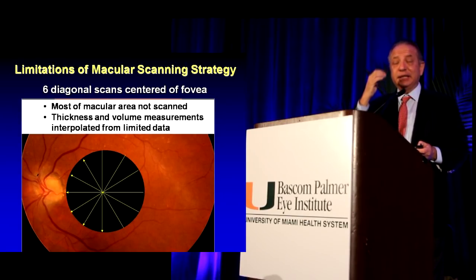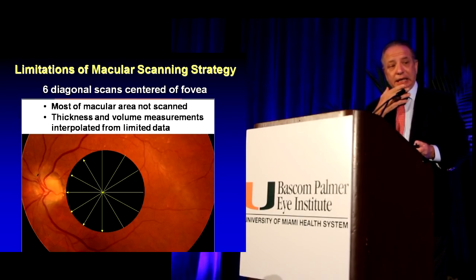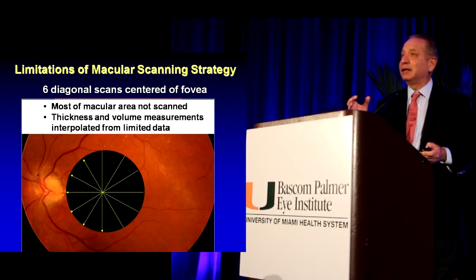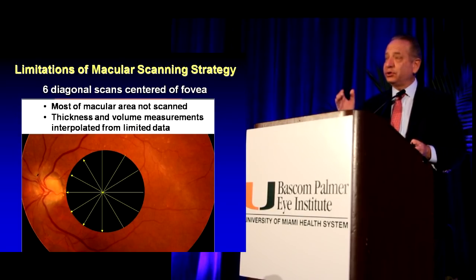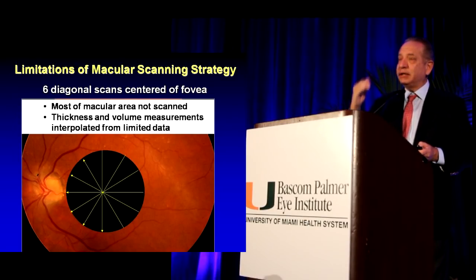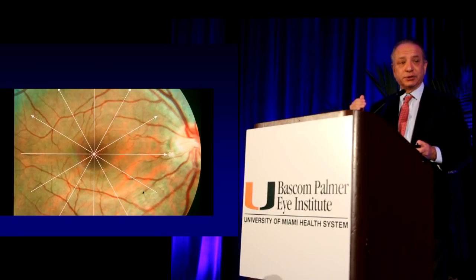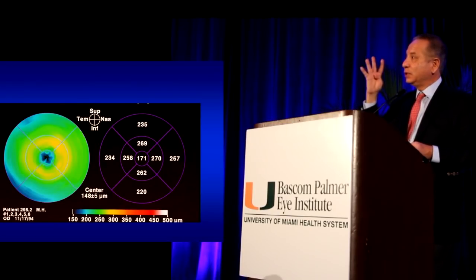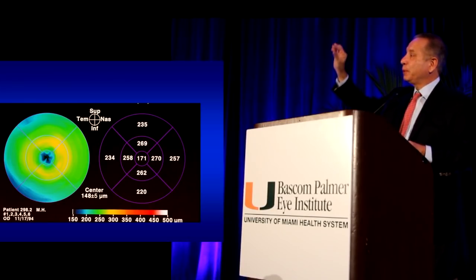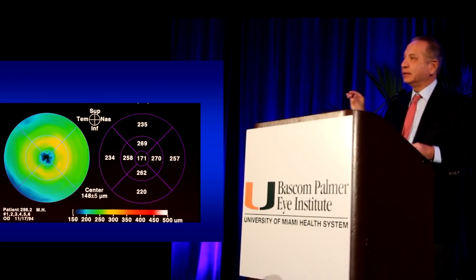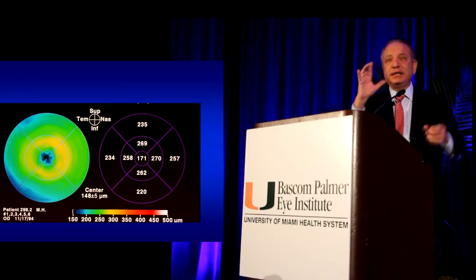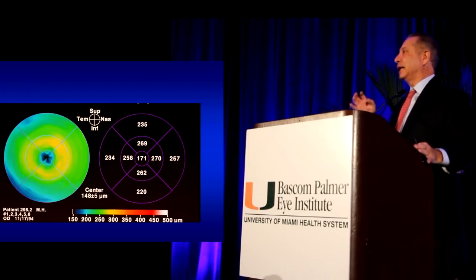This is the original Stratus machine that we invented. We looked at only six scans, and it's amazing that despite the fact that we didn't scan most of the macula, we could make very good clinical decisions. We no longer do that — we now scan the macula at 50-micron intervals and get much more detailed pictures. This is an example of the scanning strategy used to create the so-called thickness map. The original thickness maps were based on only six scans, and we interpolated or filled in the area in between.